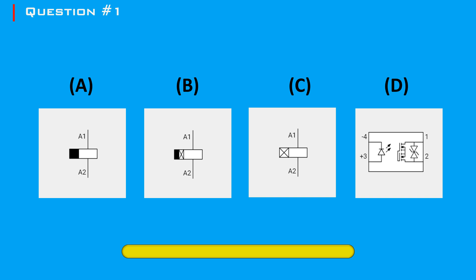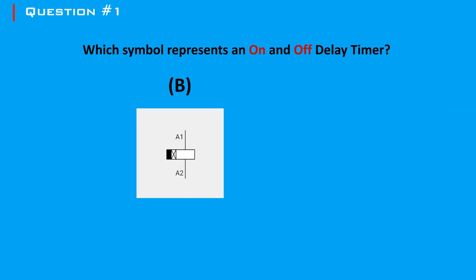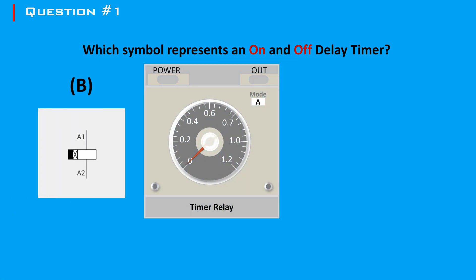Question 1: Which symbol represents an on and off delay timer? The answer is B. It is a dual-mode versatile device that can operate as both an on-delay timer and an off-delay timer. A dual-mode timer typically has a selector switch or programming option to choose between the on-delay and off-delay modes, allowing the user to configure the timer based on the specific requirements of the application.